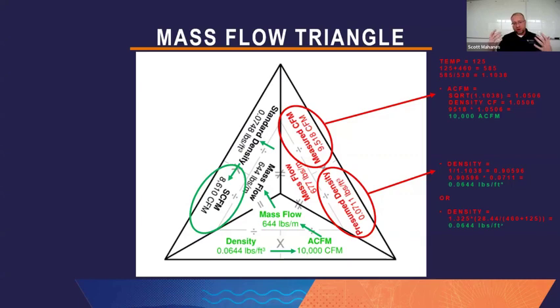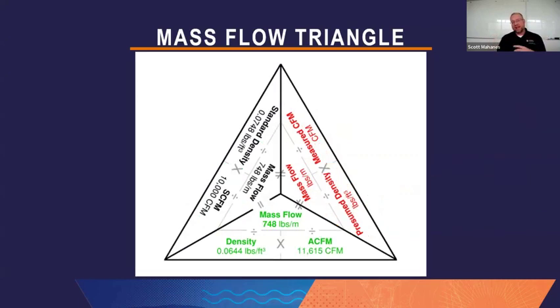Now, the triangle tool kind of helps you go reverse, convert from SCFM back to ACFM. So if I know that I need 10,000 CFM from the fan, and let's presume this is that standard density requirement, then I can take the 10,000, go reverse, multiply it by standard density, and get the mass flow target that I need. Transfer that mass flow to the actual density side, divide it by the actual density, and then I get a new targeted volumetric flow rate I need to be at to be equivalent to 10,000 standard CFM. I know this kind of gets complicated, but this is the conversion that's required to go from volumetric flow rate to mass flow rate and back. And simply, this is a decent tool that can help you do that. At least it shows you the process.